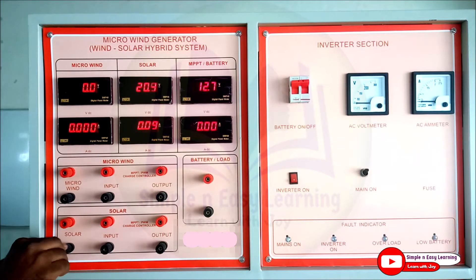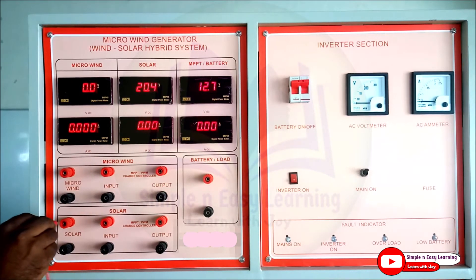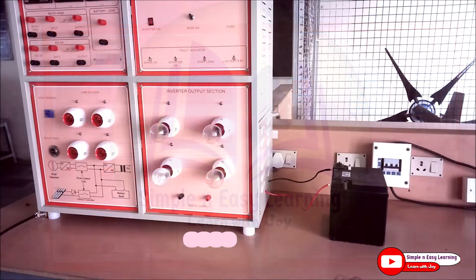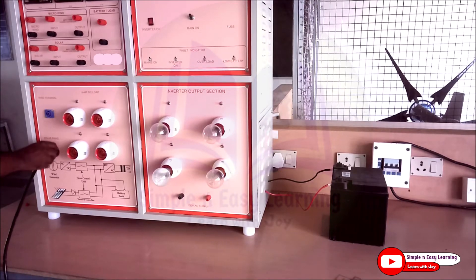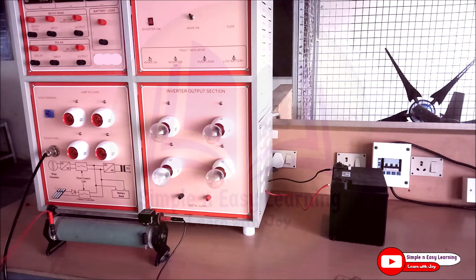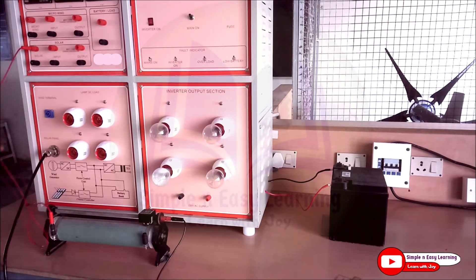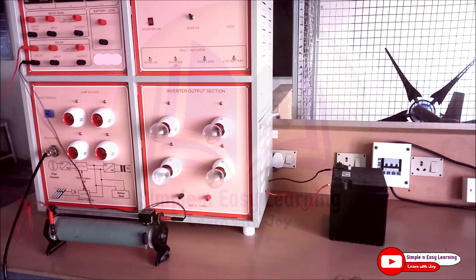Let us see the experimental setup of the solar PV system. Initially, we find the short circuit current by short circuiting the positive and negative terminals of the solar panel. It reads 4.8 amperes, so the short circuit current is 4.8 A. The cable from the solar panel is connected to the solar terminal on the inverter unit, and the loading rheostat is connected to the solar input terminals — positive and negative ends. The rheostat is kept at maximum resistance position.